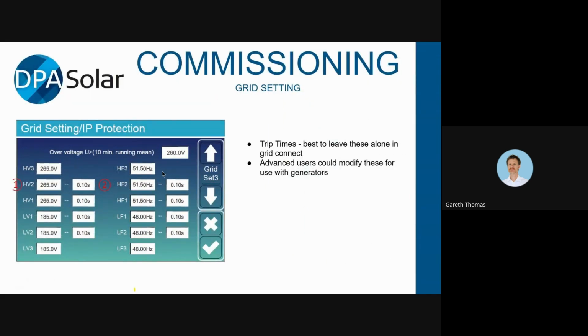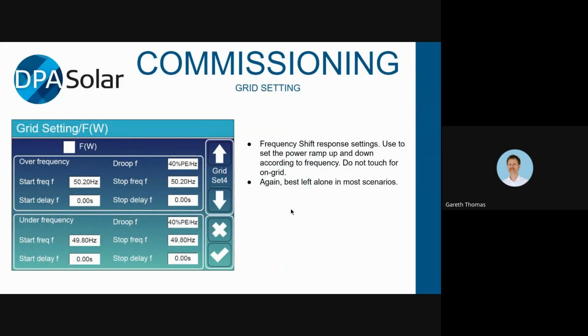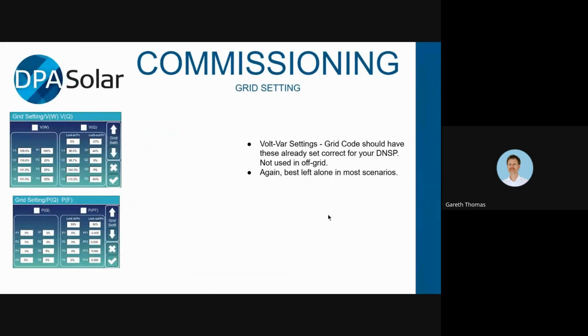This page is just the trip times for various different voltages and frequencies. You might want to modify these for use with generators, or perhaps if you were using it in an AC coupled scenario, if this was the slave. But I don't think that's a likely scenario for most of you. If you do want to do something like that, have a chat to us and we'll talk to the guys at Noark to get you any information you need on doing that.